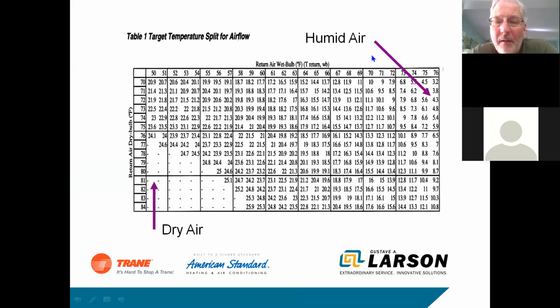So when you talk about airflow, proper airflow, it all depends on humidity and how much is in the space. So if I have a home that's 80-degree return air dry bulb and 73-degree wet bulb, my temp drop on that coil is going to be 12 degrees. Okay, as the humidity comes out of the space, as the enthalpy changes, that temperature rise is going to increase. So here, my sensible latent split is probably 40-60. Okay, as the humidity comes out of the space, my sensible latent split here is maybe 20-80, and I'm getting better airflow through the system.